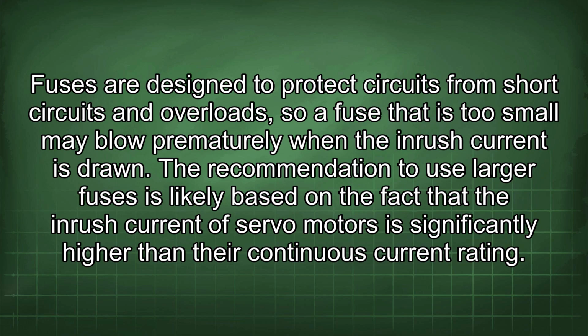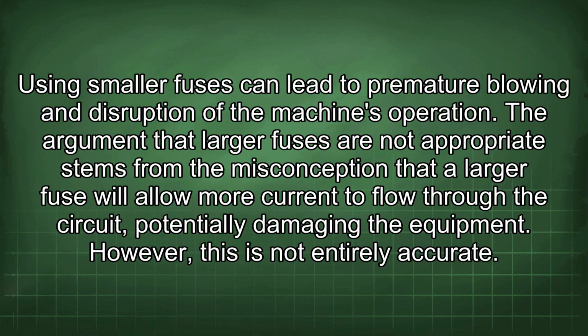The recommendation to use larger fuses is likely based on the fact that the inrush current of servo motors is significantly higher than their continuous current rating. Using smaller fuses can lead to premature blowing and disruption of the machine's operation. The argument that larger fuses are not appropriate stems from the misconception that a larger fuse will allow more current to flow through the circuit, potentially damaging the equipment. However, this is not entirely accurate.